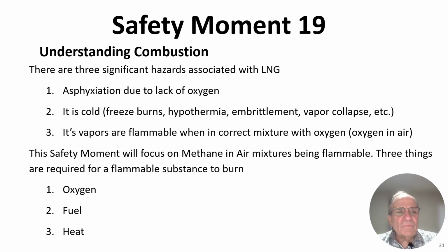Safety moment number 19. Understand combustion. There are 3 significant hazards associated with LNG. One is asphyxiation. LNG vapor is essentially methane, and if you get enough of it, it displaces oxygen, and you can be asphyxiated by a cloud of boil-off gas that does not have sufficient oxygen to sustain life.